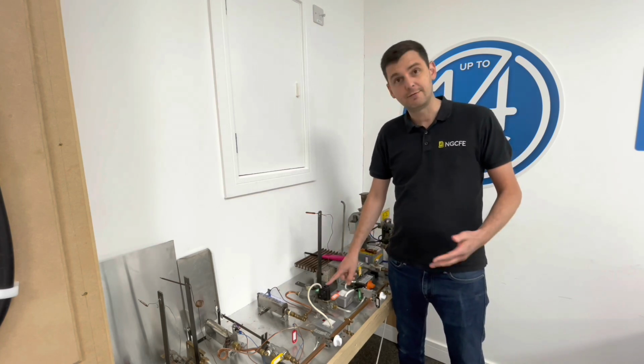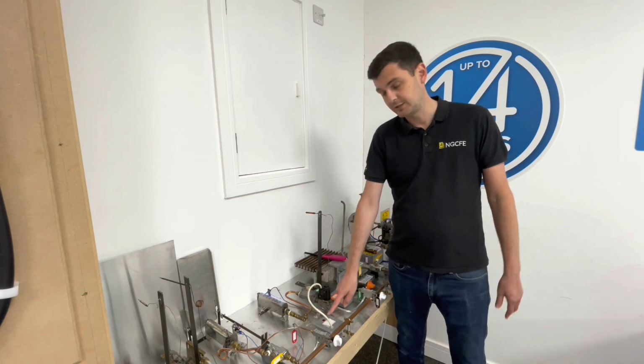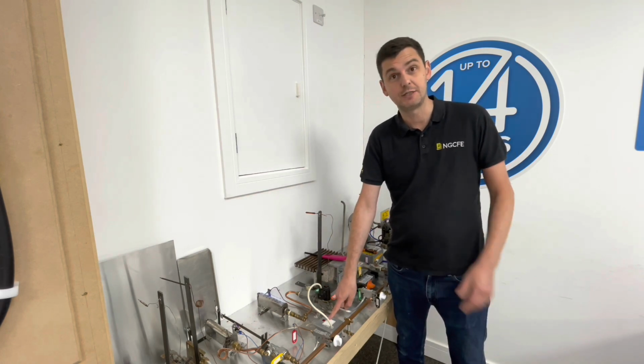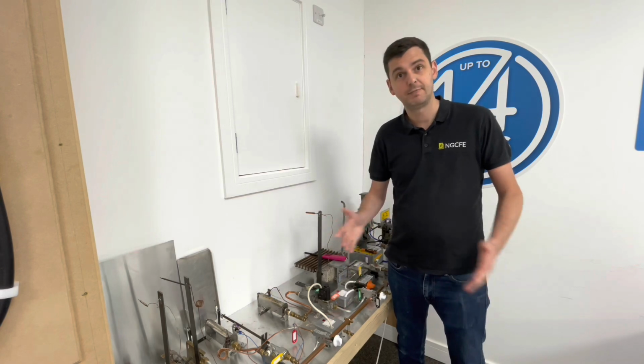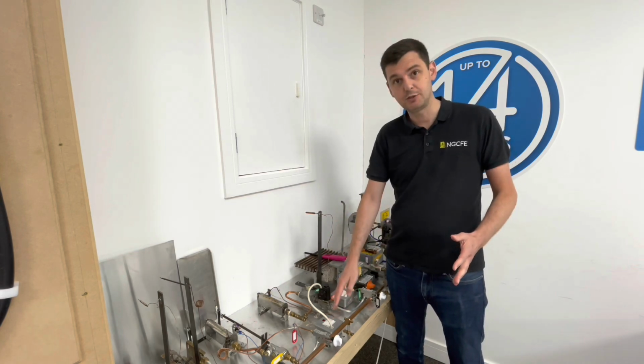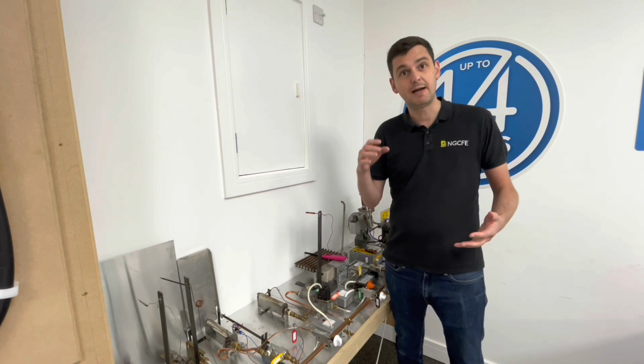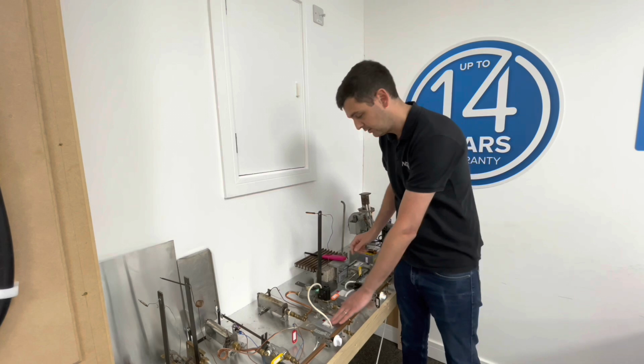Well, the solenoid valve is really straightforward. All you can do is turn the gas off, turn the electricity supply off to it. That's closed the valve, because what's happened is we've cut the electricity out, the magnet has lost its charge, and it's slammed shut. Turn it back on.